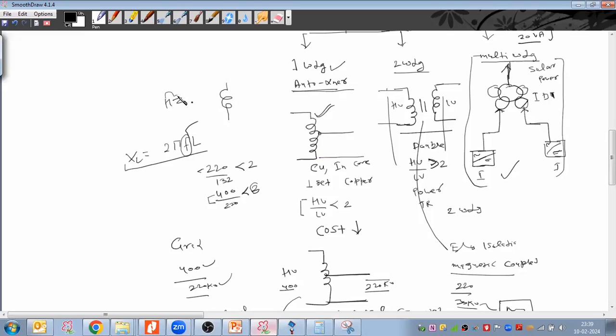I'm putting higher impedance when there is a high frequency signal, and this will have low impedance when there is a lower frequency signal. So this wave trap allows a 50 Hz signal to enter, and the wave trap will stop the high frequency signal.